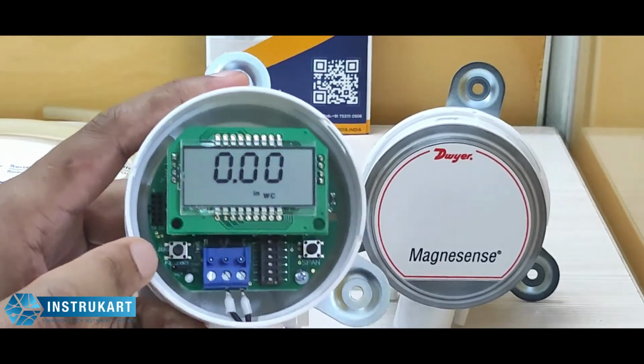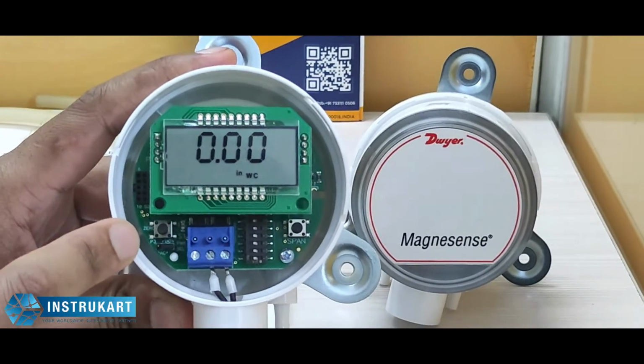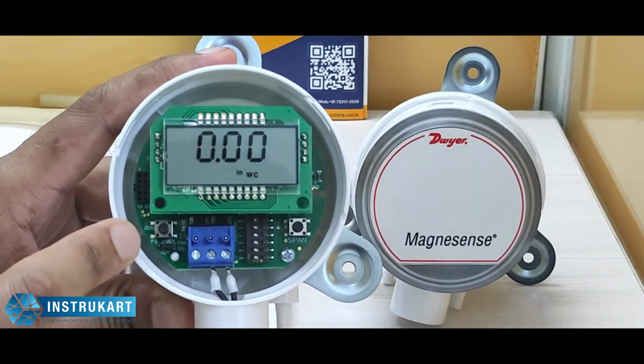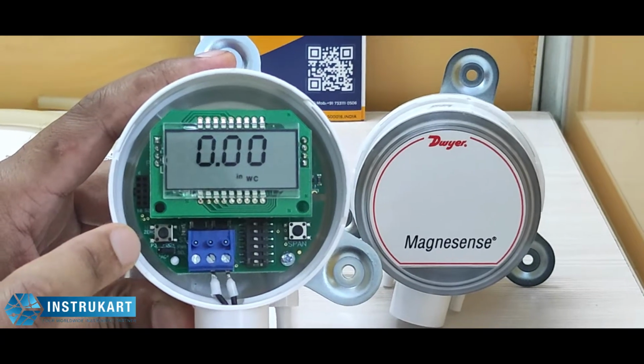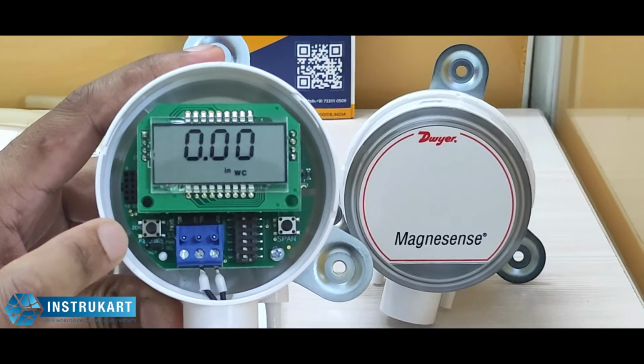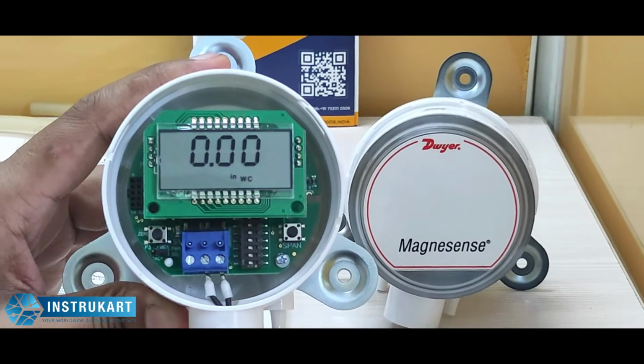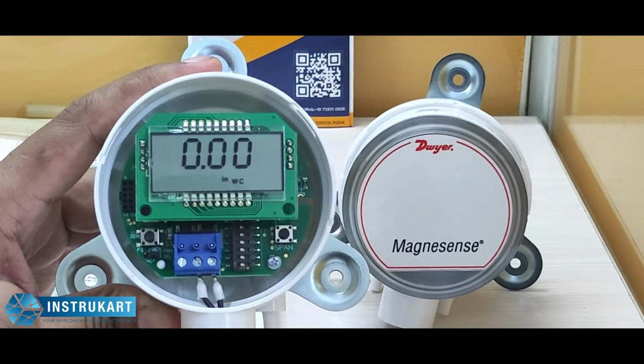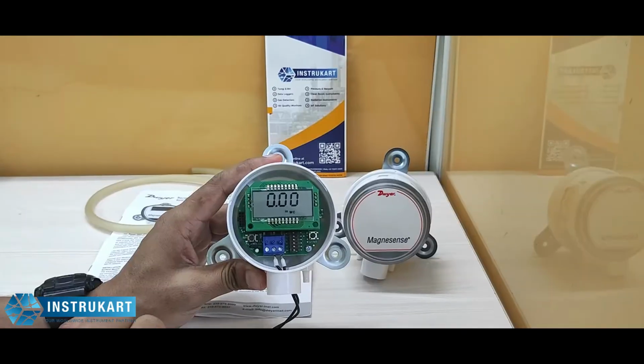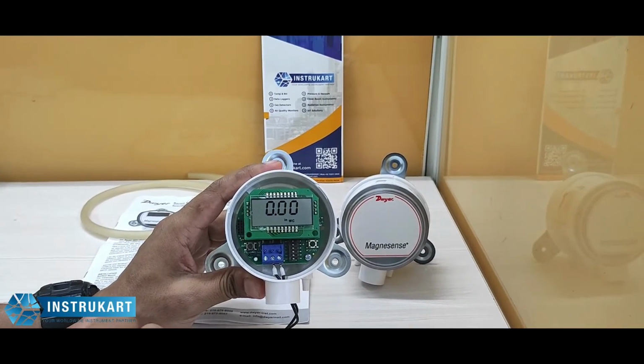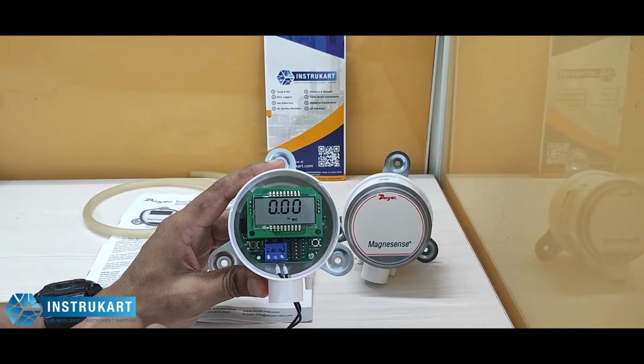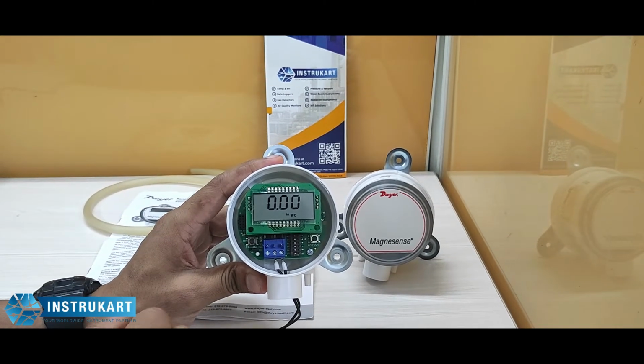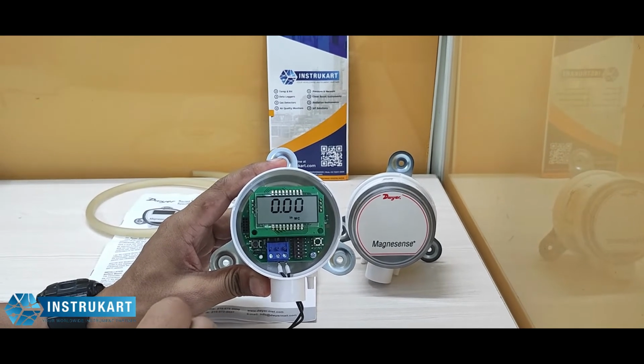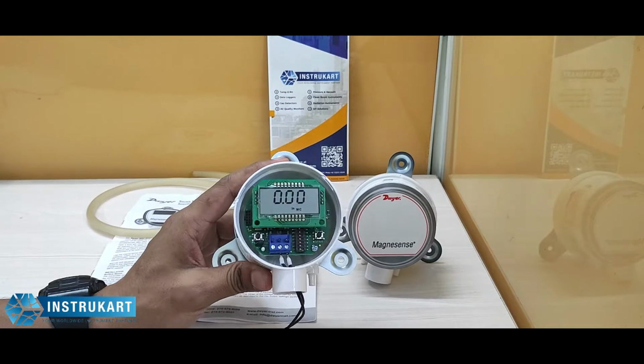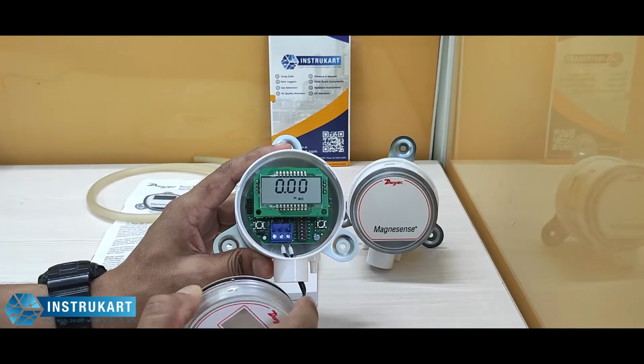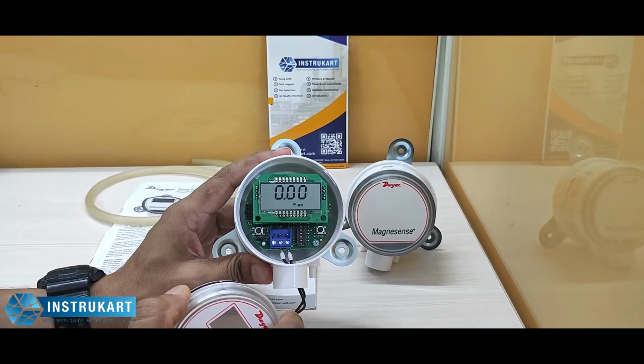It has got a stability of plus or minus 1% per year and an accuracy of plus or minus 1% on full scale for 0 to 0.15 inches water column or 40 Pascal. The temperature limit is 0 to 150 degrees Fahrenheit, which means it is operated between minus 18 to 66 degrees Celsius. You can use the media as air or non-combustible compatible gases for this.